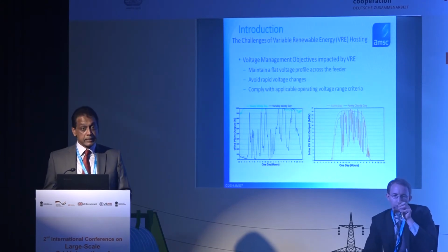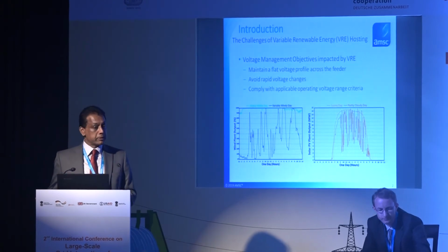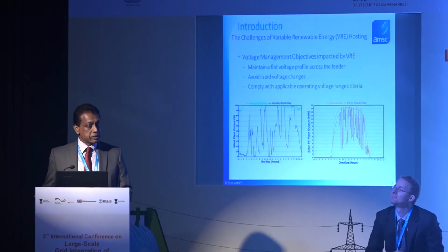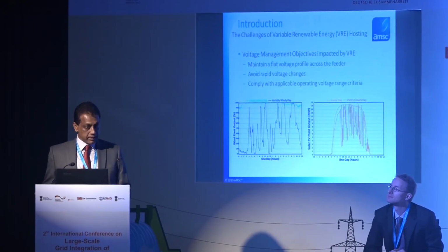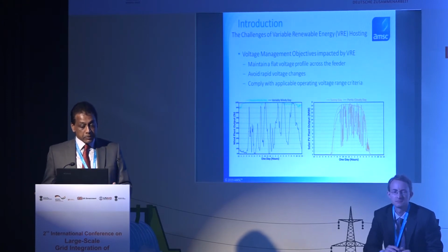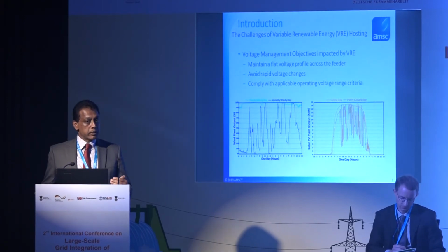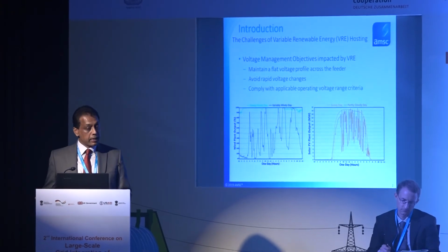We have a STATCOM system installed at this plant as well. We did exhaustive studies to understand how fast that change happens, and along with the customer and the data taken from NREL, the impact on the system voltage was just too great for the utility to handle.